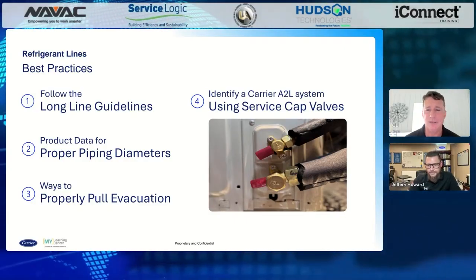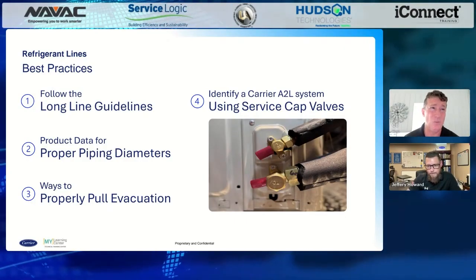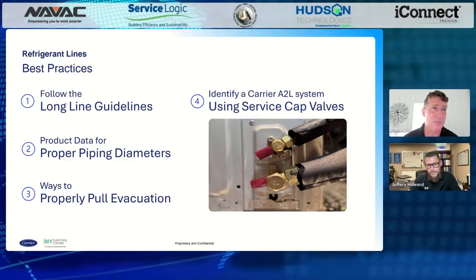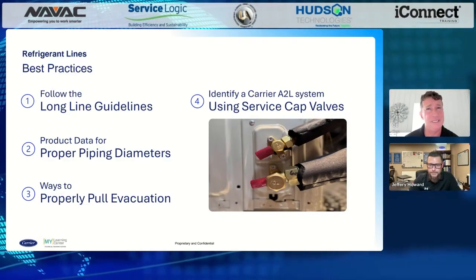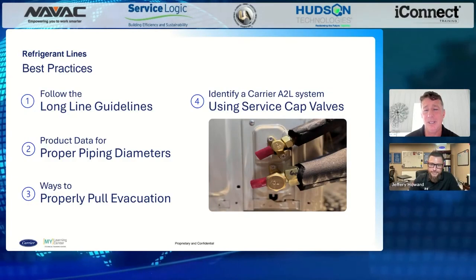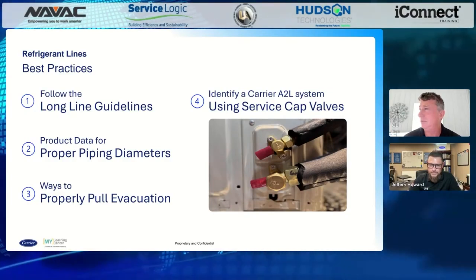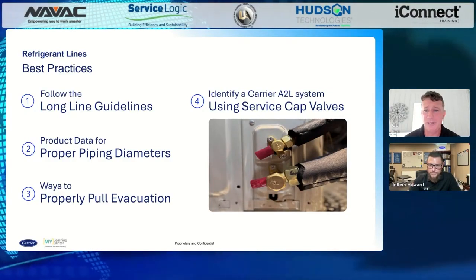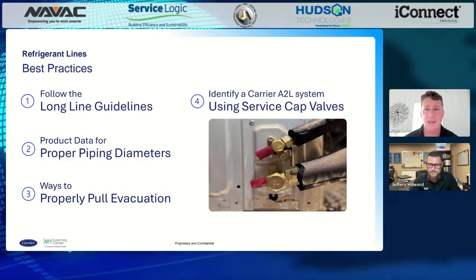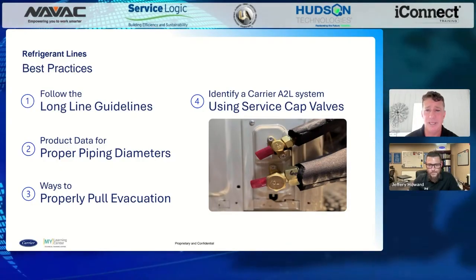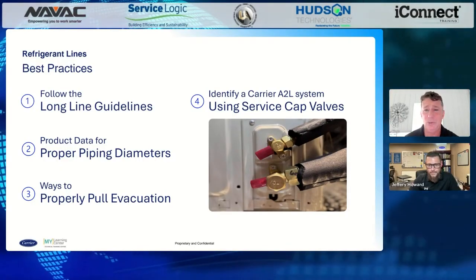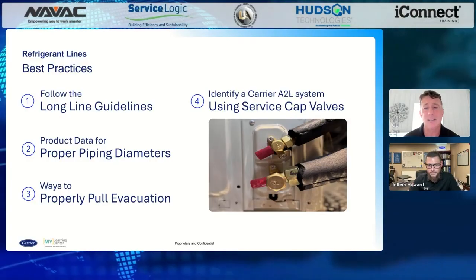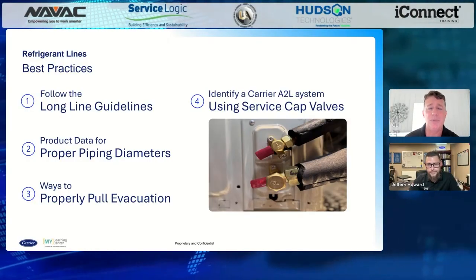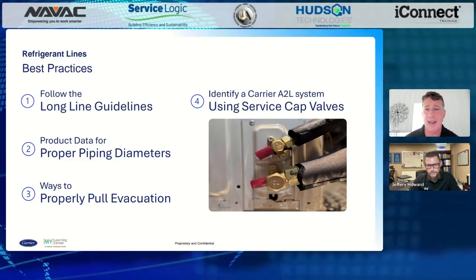Absolutely. Yeah, I've done a few videos. It's been a while since I did one on the smaller vacuum pumps. I did one years ago with a 2 CFM rechargeable vacuum pump and a 15-foot line set on a 3/8, 3/4, and had 250 microns in like 4 minutes. Doing it properly can change your speed drastically.